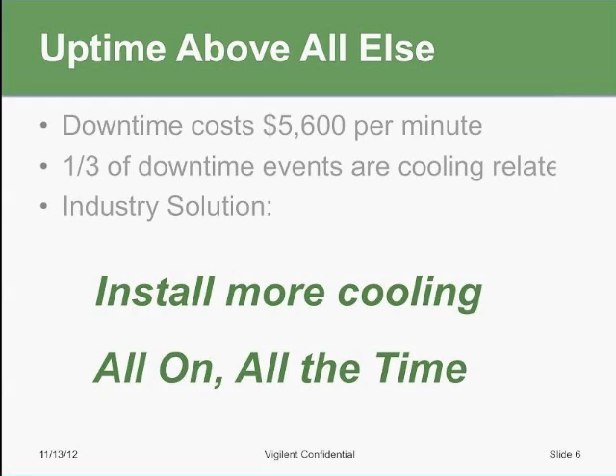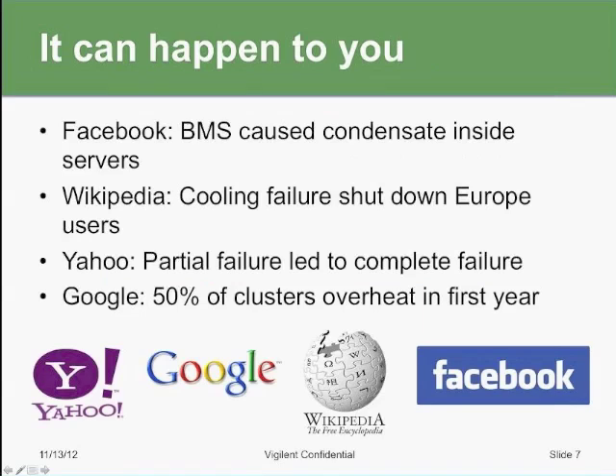Here are some case studies from some sophisticated IT and data center owner-operators that have had operational outages recently. And the one that I'm going to mention quickly is the Facebook data center up in Prineville, Oregon, where a BMS glitch had caused the outside air dampers to close, which caused condensation to build up in the IT equipment and causing some of that equipment to fail. Now, Facebook, being a pretty sophisticated data center owner-operator, and they probably had a pretty sophisticated cooling system with enough capacity, encountered an operational issue or an operational redundancy issue that caused an outage in that facility.